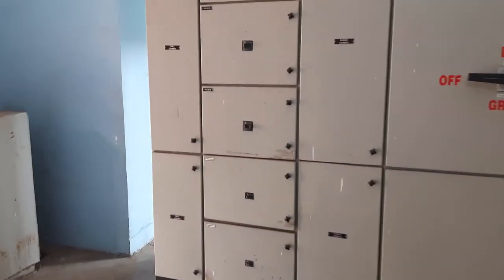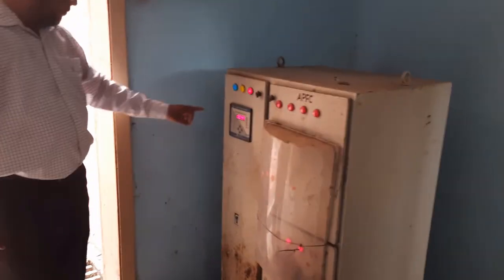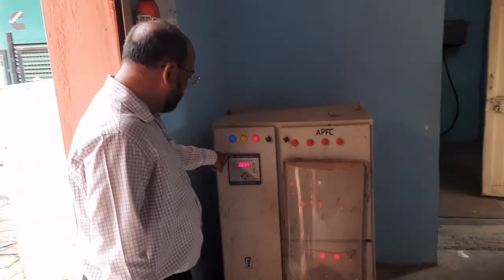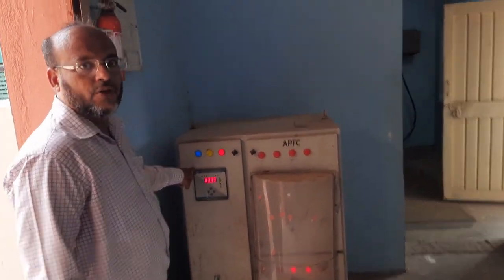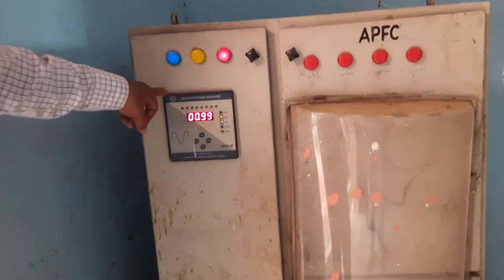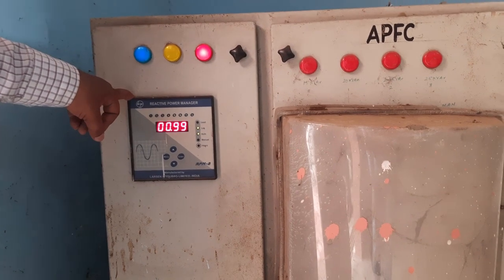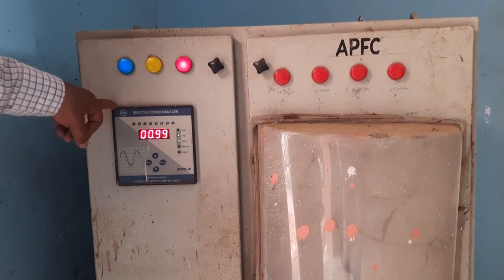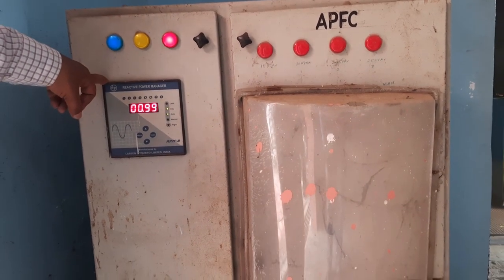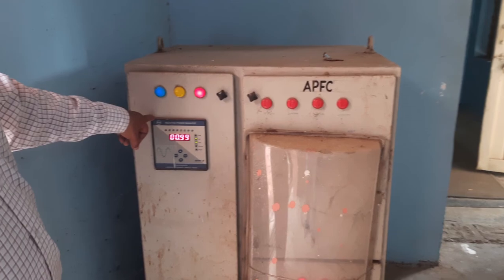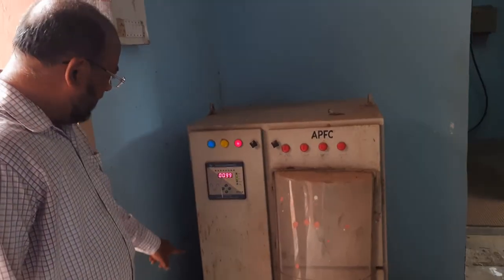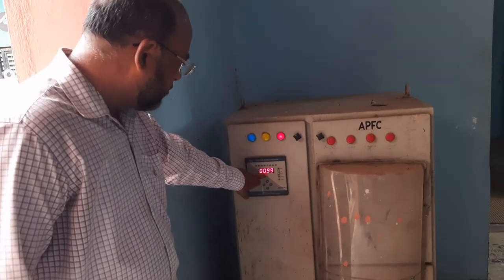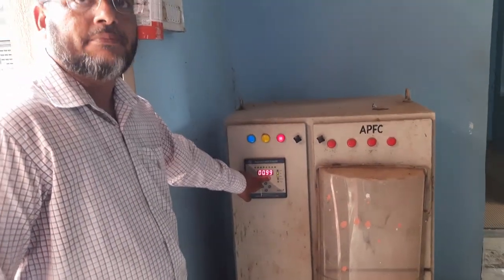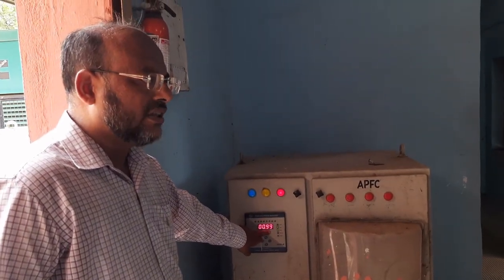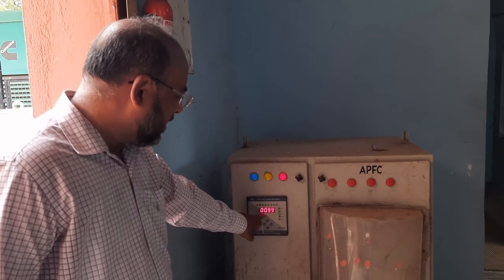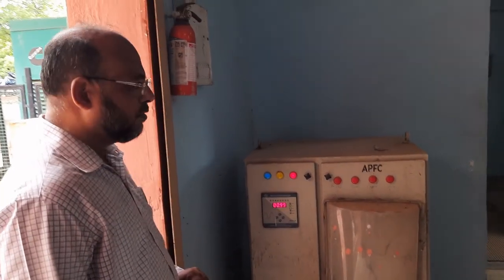Now this is the APFC, automatic power factor controller. Nowadays MSEDCL and all utility sectors charge electricity on kVAh billing. Earlier it was kilowatt billing, nowadays it is kVA. Therefore it is very necessary to maintain the power factor, both leading and lagging. The automatic power factor controller comprises 100 kVAR in different stages, right from 5 kVAR and 3 kVAR, for smooth variation. Here the power factor is 0.99 lagging, which is somewhat ideal. Ideal is 1, but it does not remain 1 since the load is continuously varying with time. A power factor of 0.99 is appreciably good.